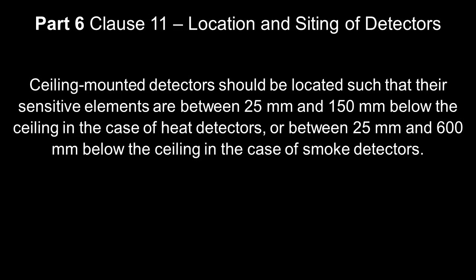We don't want to put them over the stairs, as that's going to compromise safety and we can't get access. So we've got to put them in sensible places. It's really important. Ceiling mounted detectors should be located such that their sensitive elements are between 25mm and 150mm below the ceiling in the case of heat detectors, or 25mm to 600mm below the ceiling in the case of smoke detectors.